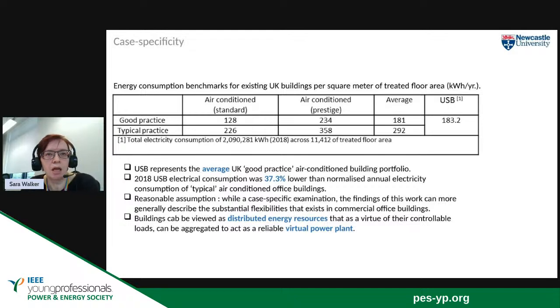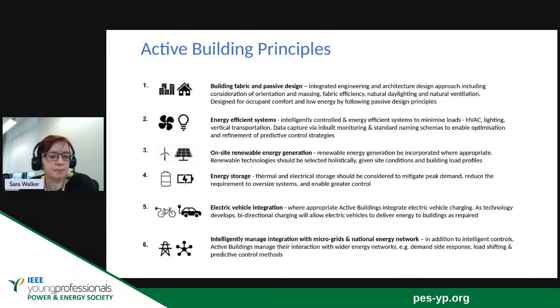Is our building absolutely brilliant compared to the typical? Actually, no. So the USB, in terms of its energy consumption in kilowatt hours per year, is fairly close to an average good practice building. It's not the absolute best spec possible. So it's fairly typical, and therefore we feel it was a good case study to use to reflect typical behaviours of commercial office buildings. So I think that enables us to say that the building could, through controllable load, offer some behaviours that look like virtual power plants.